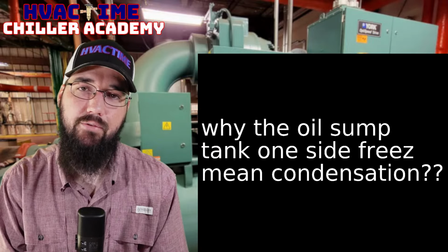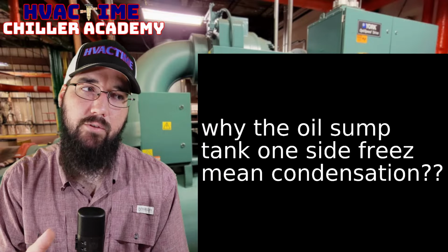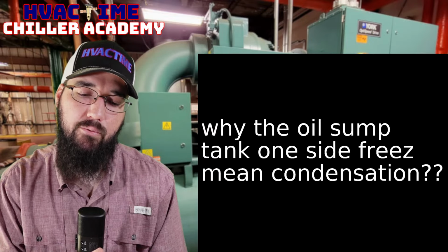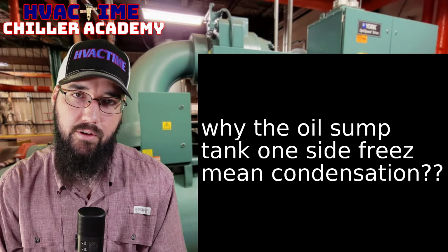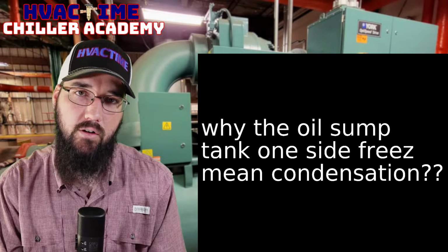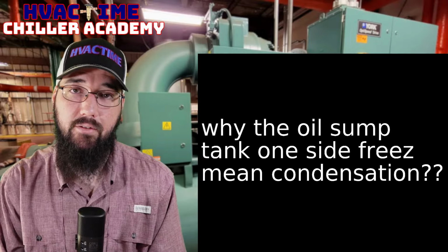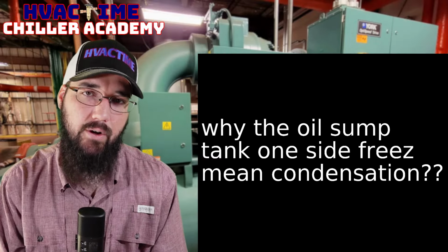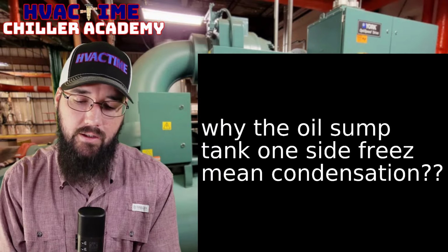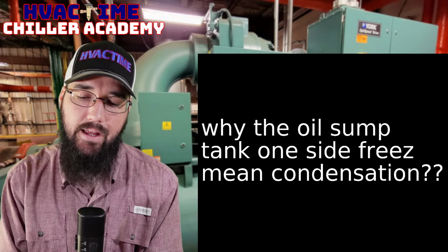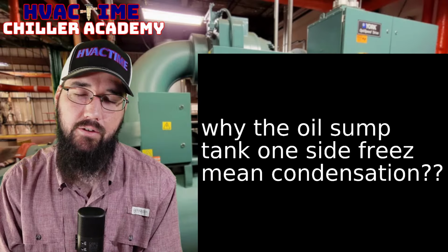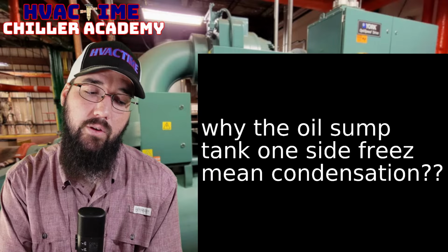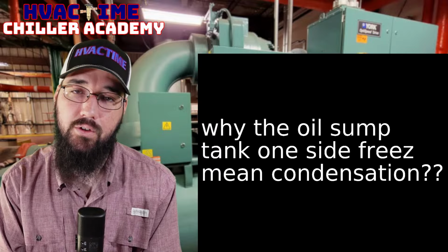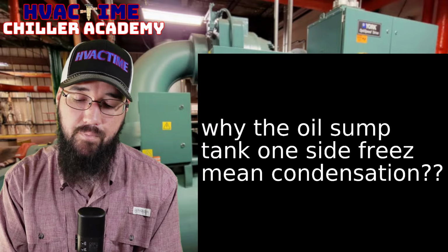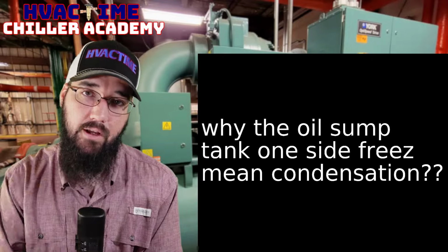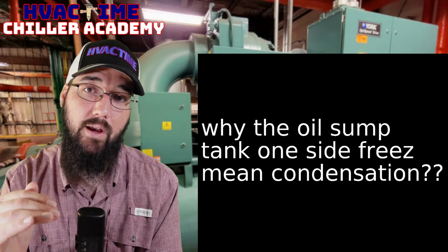which is why we have to pay attention and make sure that we're feeding refrigerant correctly through the eductor, because we can overload it with liquid refrigerant from the evaporator, and that goes directly into our sump. And so what you'll see on a YK is if you're overfeeding liquid into the sump, your oil temperatures will start running lower, and you'll actually see the top of the sump housing in some cases begin to sweat and even ice.